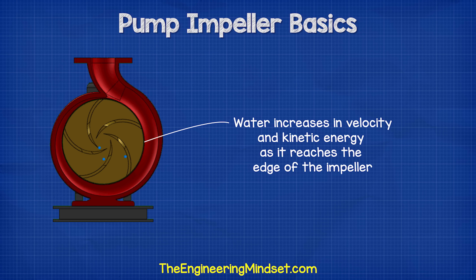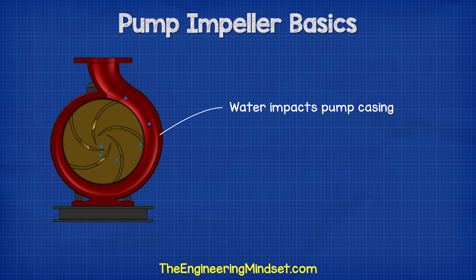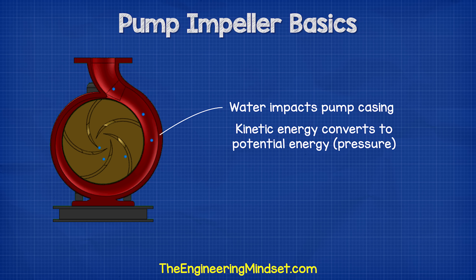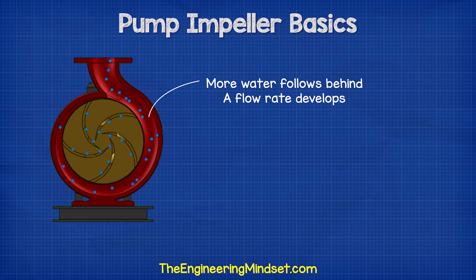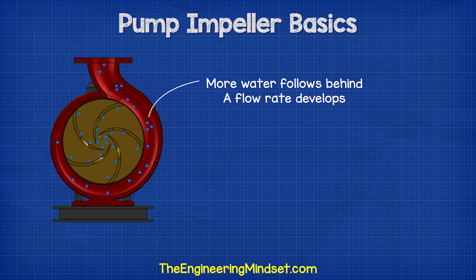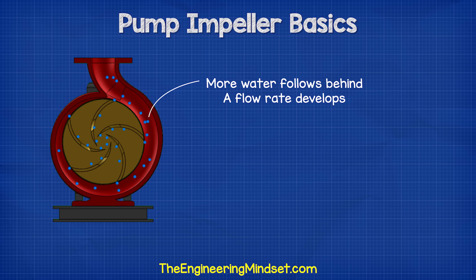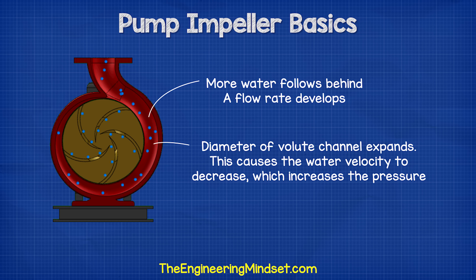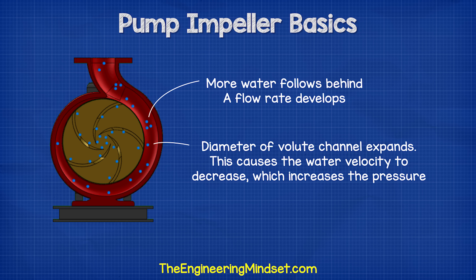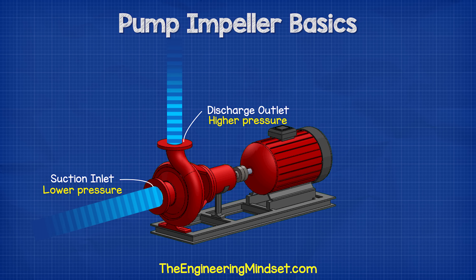This high-speed water flows off the impeller and into the volute, where it hits the wall of the pump casing. This impact converts the velocity into potential energy or pressure. More water follows behind this and so a flow develops. The volute channel has an expanding diameter as it spirals around the circumference of the pump casing. As it expands, the velocity of the water will decrease, resulting in pressure increasing. This expanding channel therefore allows more water to keep joining and converting into pressure.